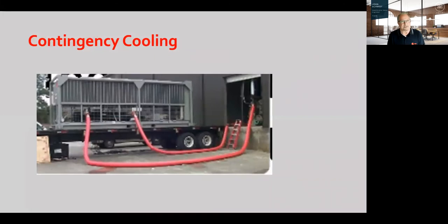Another piece of redundancy is contingency cooling. Basically what that is, is extending your pipes, both electrical and chilled water and even condenser water, to a location that makes it a little bit easier to bring in a rental chiller should you need it, or even a permanent chiller. They end up being permanent oftentimes, at least for an entire summer. But in the event of a catastrophe to the chilled water plant, or 1 or 2 chillers go down, you can connect a rental chiller to that system within 4 or 5 hours. And you can usually get a rental chiller within a day. Next slide.